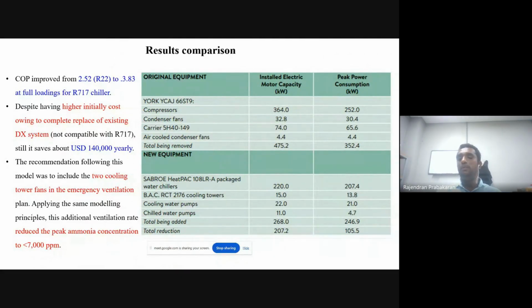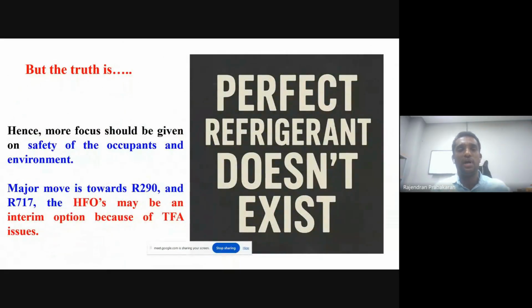Both the systems performed well compared to the earlier one, and it showed an improvement in COP from 2.52 to 3.83. Because of less power consumption and improved cooling efficiency, it also saved about 1,40,000 USD yearly. But the one criterion is we need to use additional ventilation with a good rate to reduce the ammonia concentration within the cooling area. So overall, from all these results, we can see that no perfect refrigerant exists.